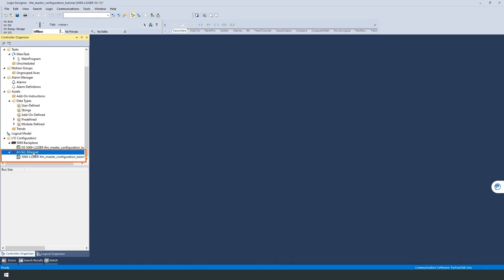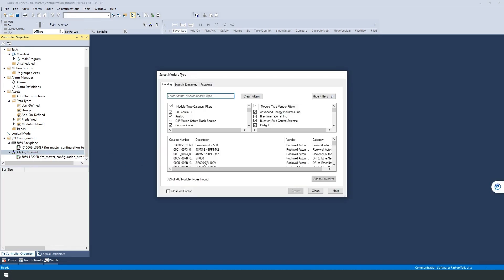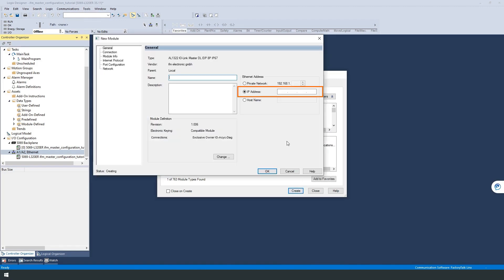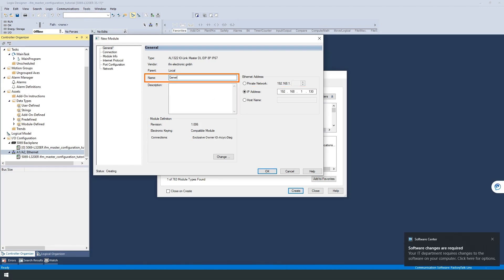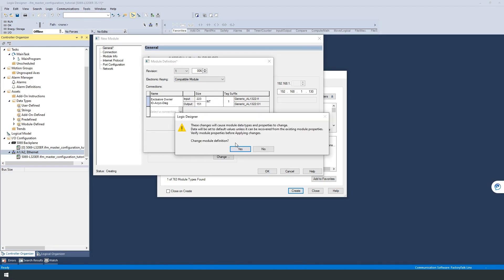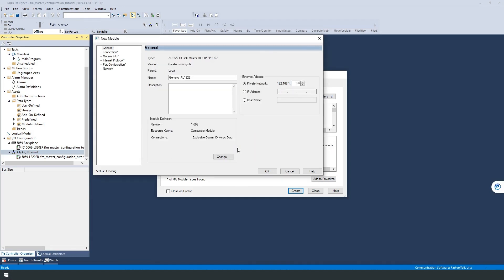Right-click on the Ethernet adapter, to which we are connected, and add a new module. Use the search bar to navigate to the AL1322. In the module properties, we enter the IP address of the master that we have previously set. We choose and assign the name GenericAL1322 for our IO-Link master. We also change the data type from short integer to integer to be able to work with a 16-bit, instead of an 8-bit view. When all settings are confirmed, the module is added on the left side.